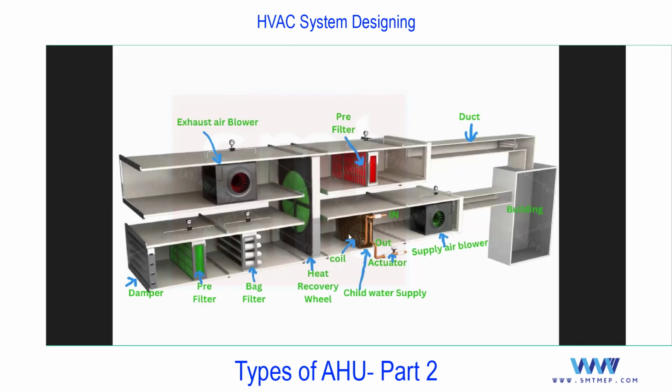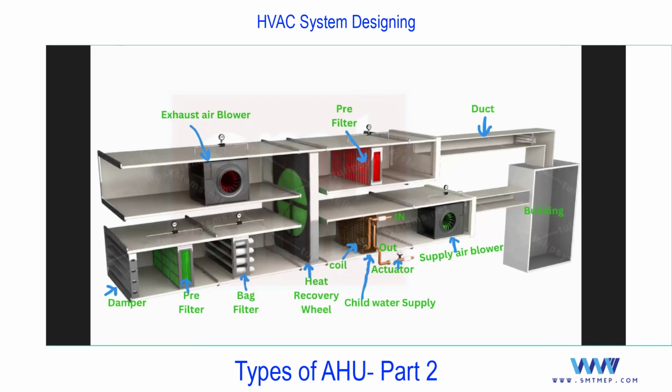You can try to understand with this. First of all, the new component in this is a heat recovery wheel, or a thermal wheel, and this wheel will rotate slowly. It will rotate with a small motor connected to this. Okay. So this side is new. Right side, you can consider as a normal AHU. So you see here, this is the return air, and partly you can consider like this. Some amount of air we are going to exhaust, equal to what? Equal to the fresh air.